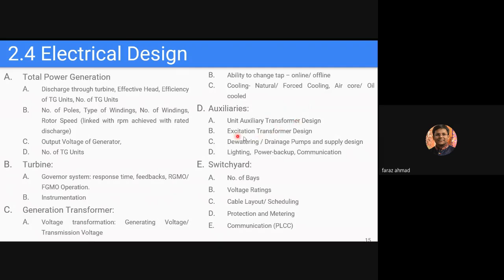Then there is the excitation transformer. You have the field windings on the rotor, which you need to regulate so as to meet all the reactive power demand of the grid. You change it accordingly, that's what excitation transformer design comes in.